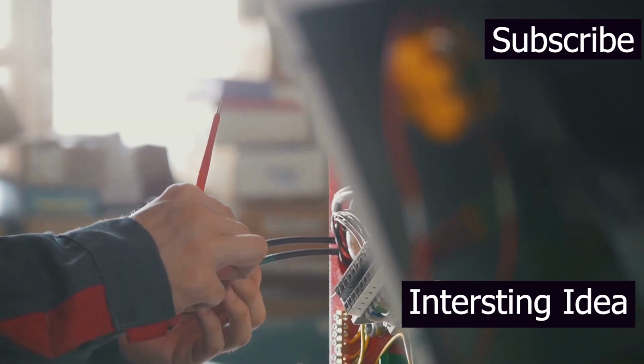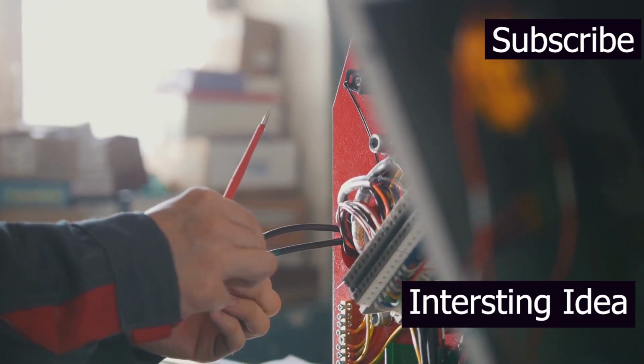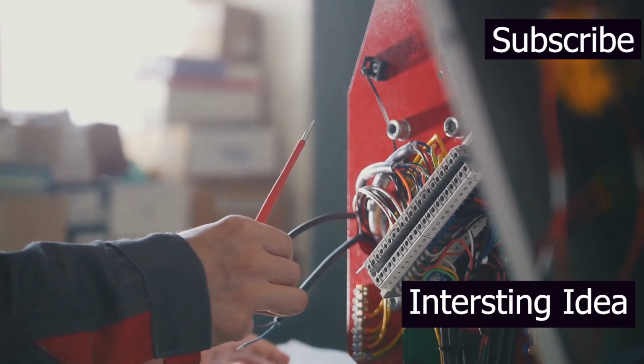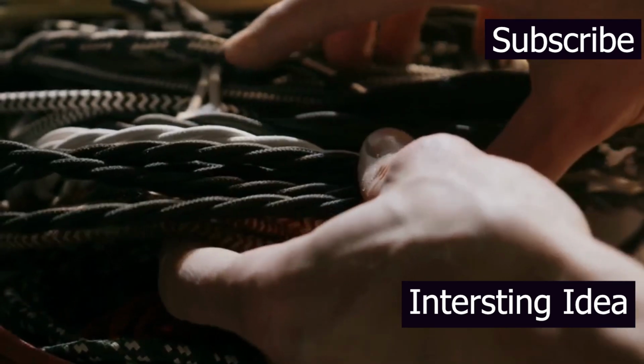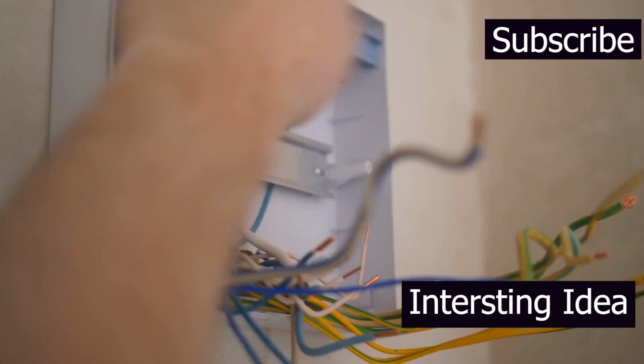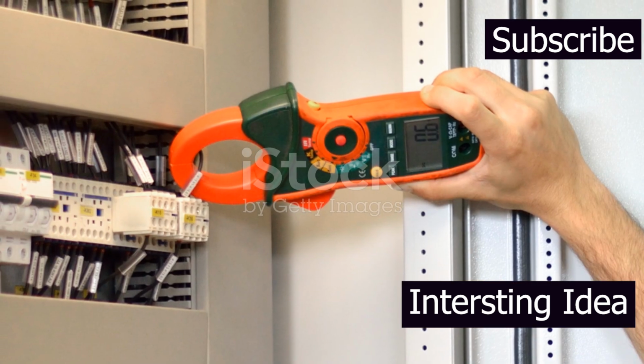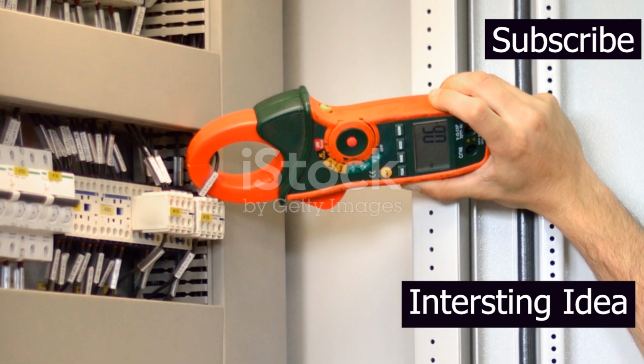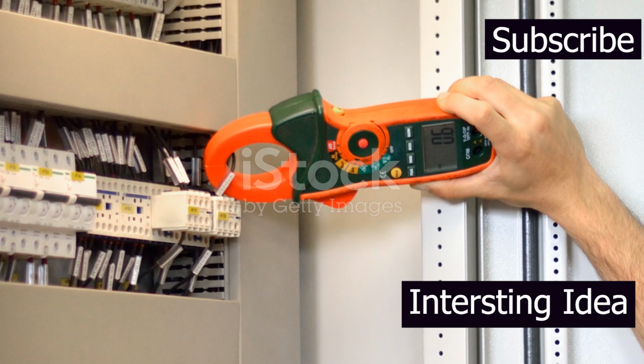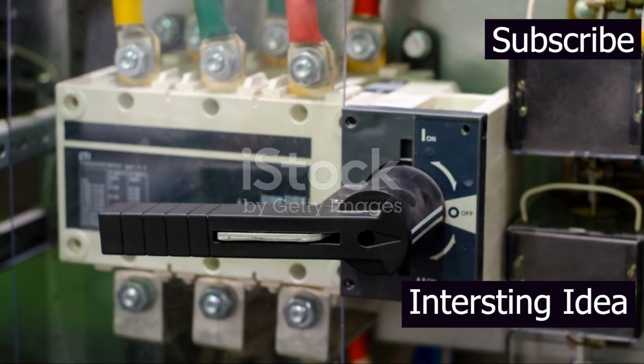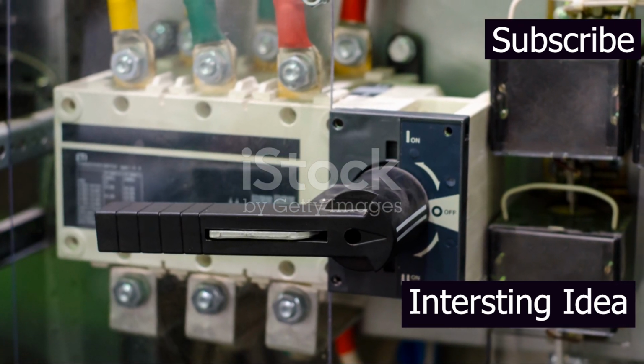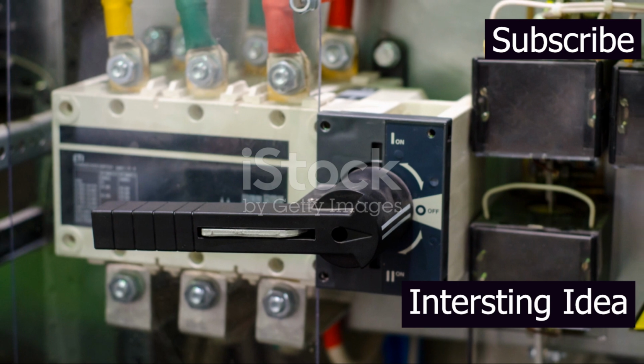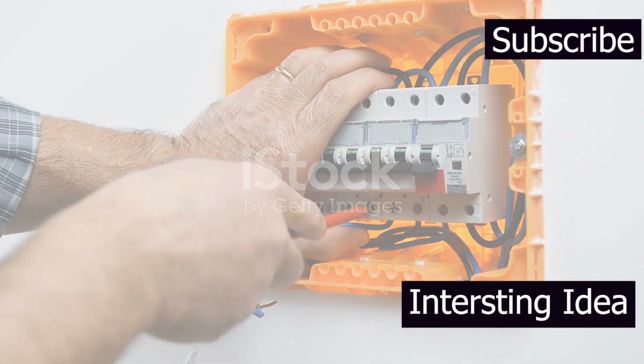Once the breakers are in place, connect the wires from each circuit to their corresponding breakers. Use the correct wire gauge for the amperage of the circuit. Securely tighten the terminal screws to prevent loose connections. Remember, using the correct amperage rating for each circuit breaker is crucial for safety. Never replace a breaker with a higher amperage rating than the wire size allows, as this can lead to overheating and fire hazards.